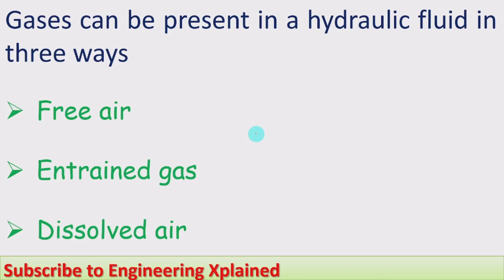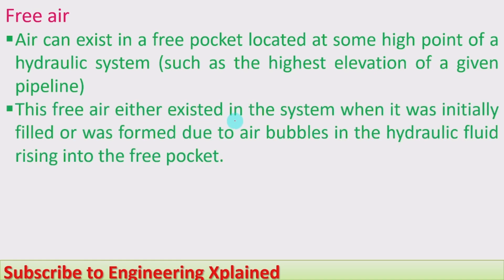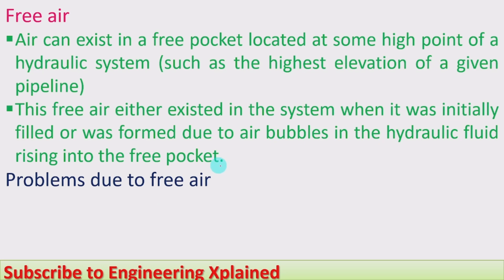The gases can be present in the hydraulic fluid in three ways: free air, entrained gas, and dissolved gas. The first one is free air, which can exist in a free pocket located at some high point of the hydraulic system, such as the highest elevation in a given pipeline. At the top position, air has lower density and will exist in the form of pockets. This free air either existed when the system was initially filled or was formed due to air bubbles rising into a free pocket during filling or operation.